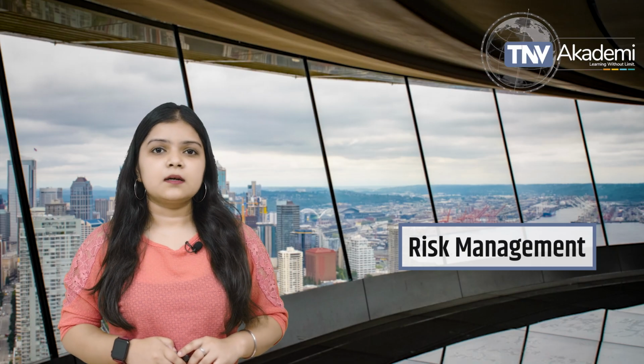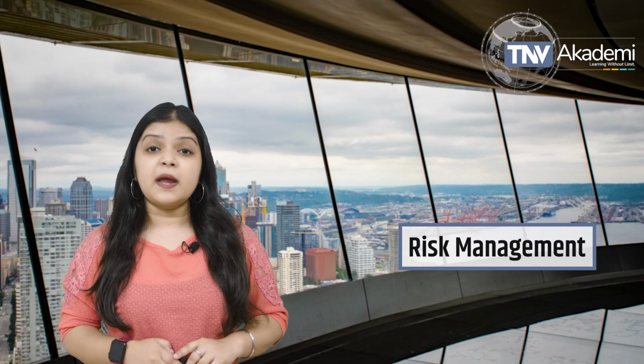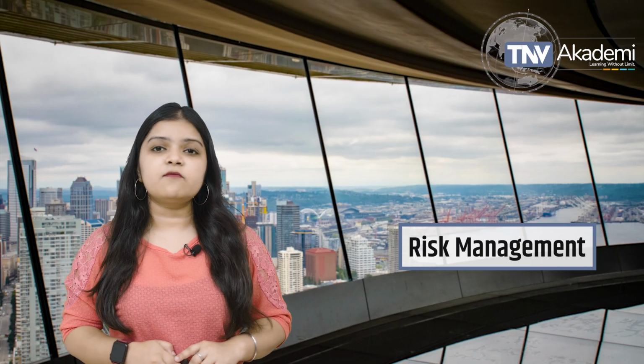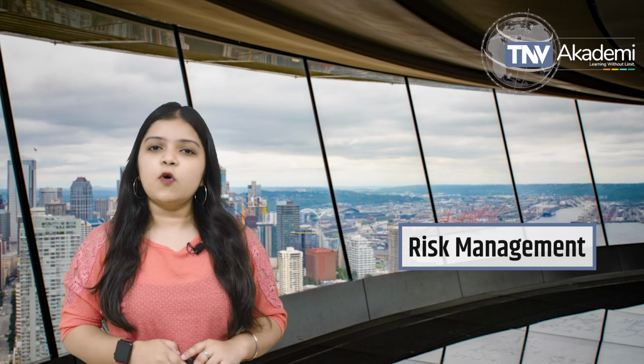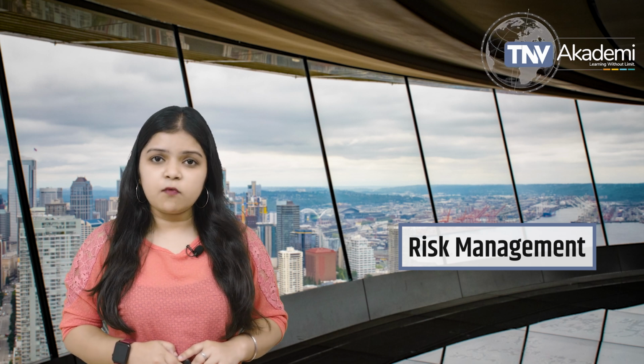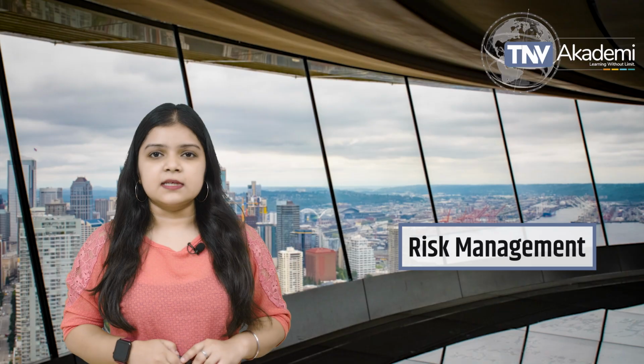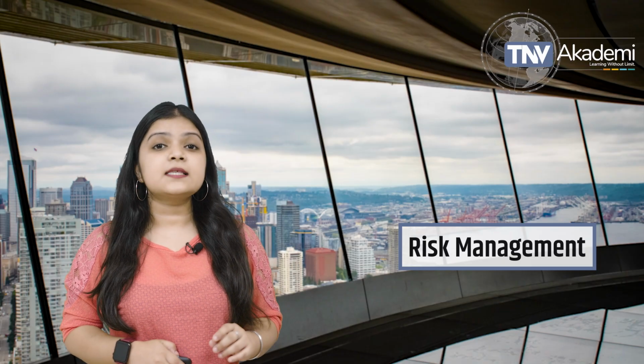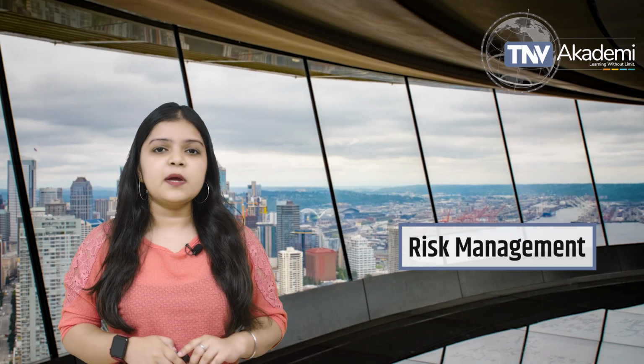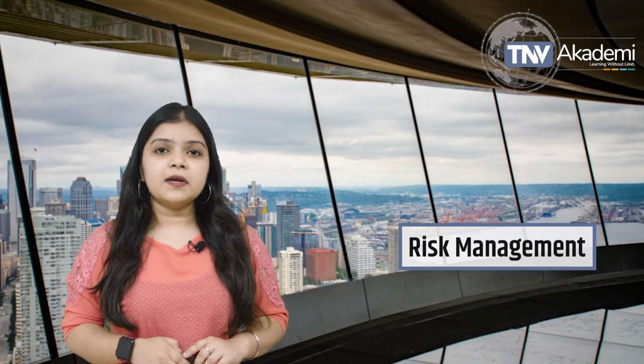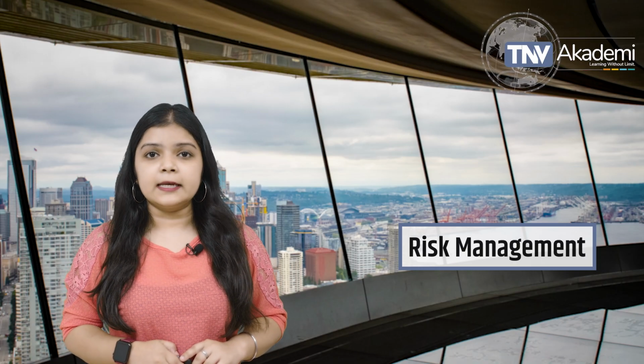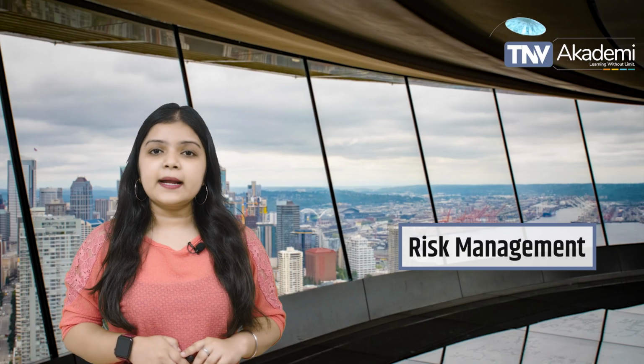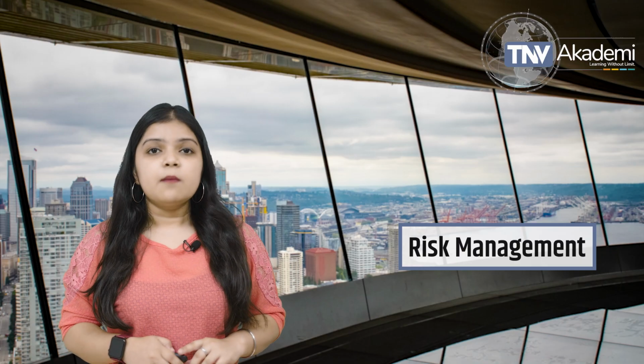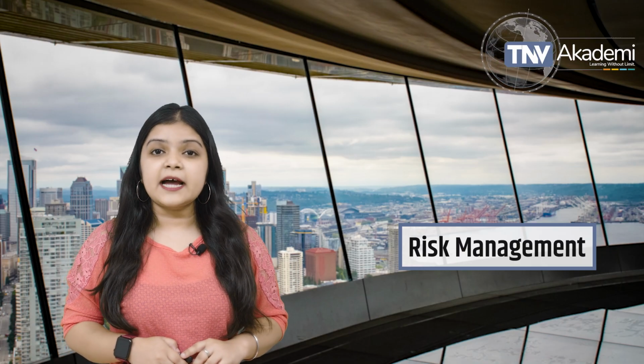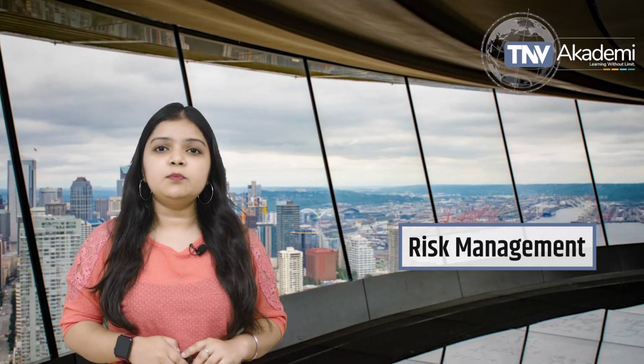Risk management. Strengthens risk management. Medical devices come with potential safety risks, and ISO 13485 helps companies identify, assess, and mitigate those risks. The standard requires a risk-based approach to product design and manufacturing. Continuous monitoring of customer complaints and product failures. Procedures to ensure quick corrective actions if issues arise. By following these principles, companies can prevent recalls, safety issues, and legal problems down the line.